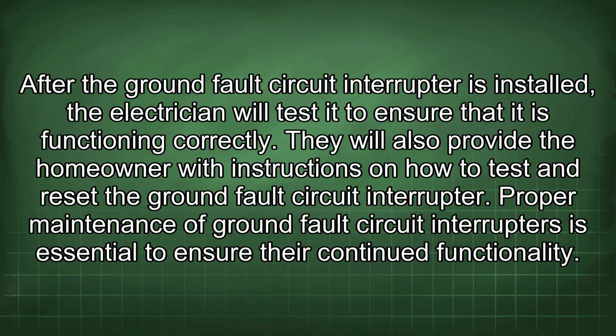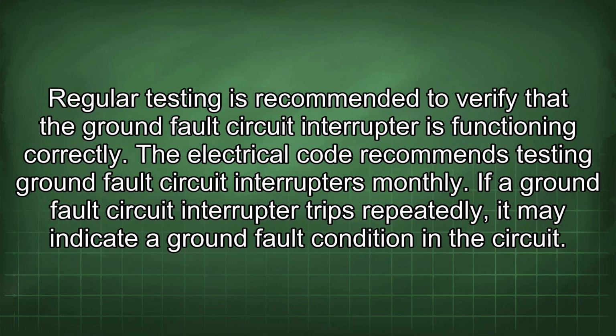Proper maintenance of ground fault circuit interrupters is essential to ensure their continued functionality. Regular testing is recommended to verify that the ground fault circuit interrupter is functioning correctly. The electrical code recommends testing ground fault circuit interrupters monthly.